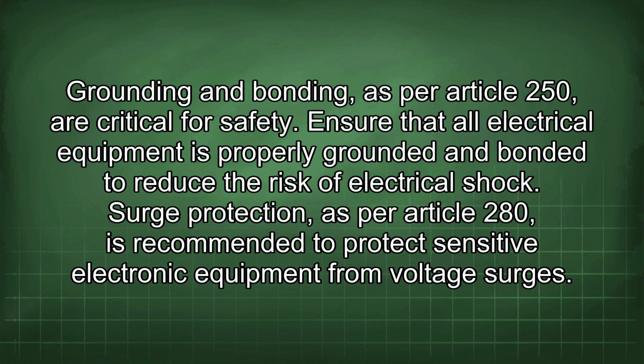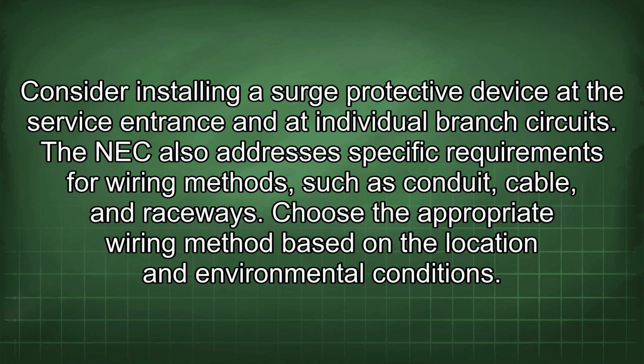Surge protection, as per Article 280, is recommended to protect sensitive electronic equipment from voltage surges. Consider installing a surge protective device at the service entrance and at individual branch circuits. The NEC also addresses specific requirements for wiring methods such as conduit, cable, and raceways. Choose the appropriate wiring method based on the location and environmental conditions.